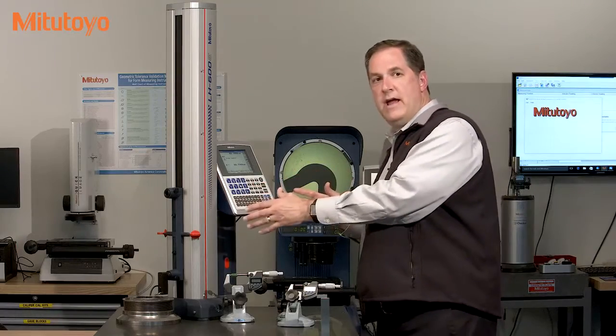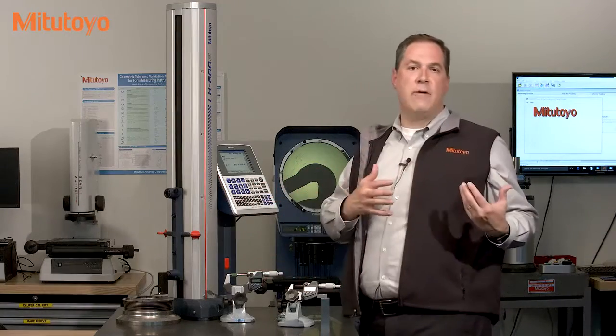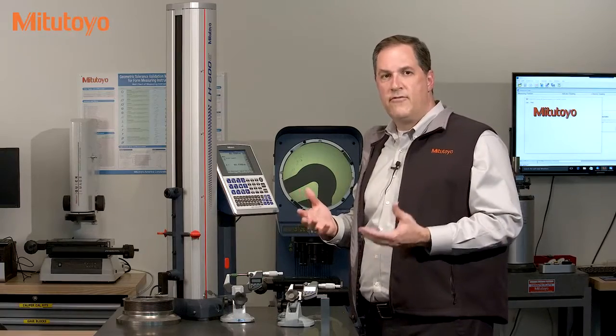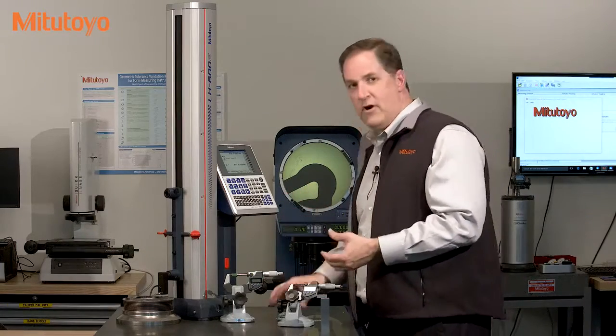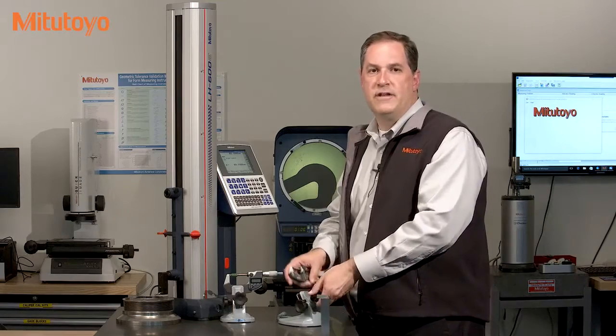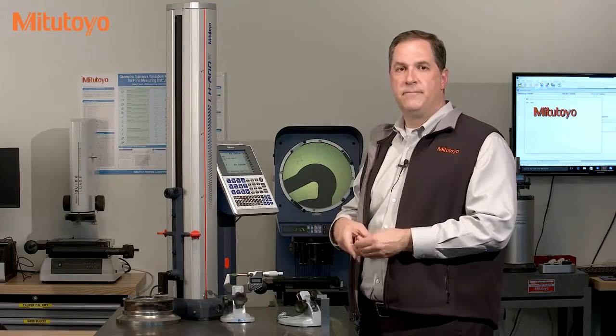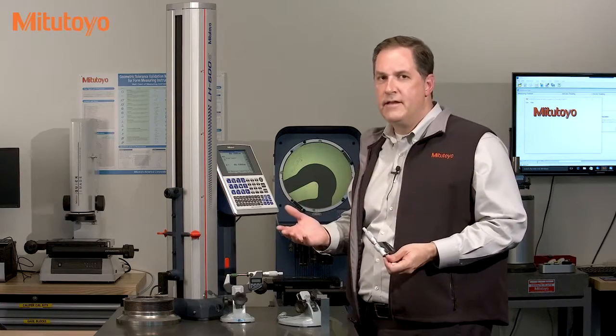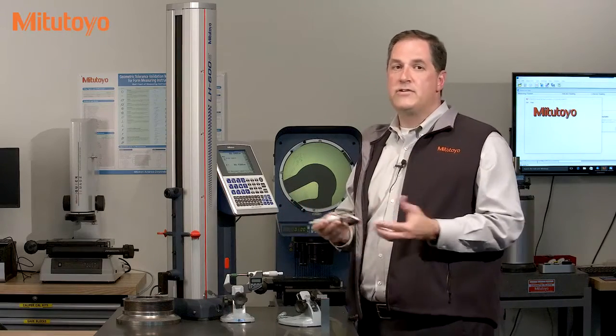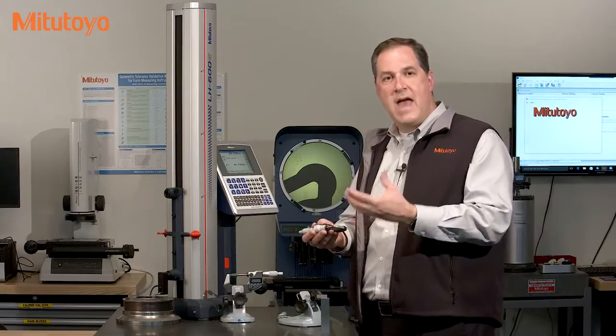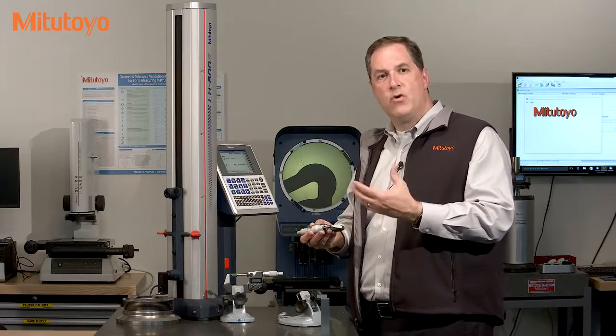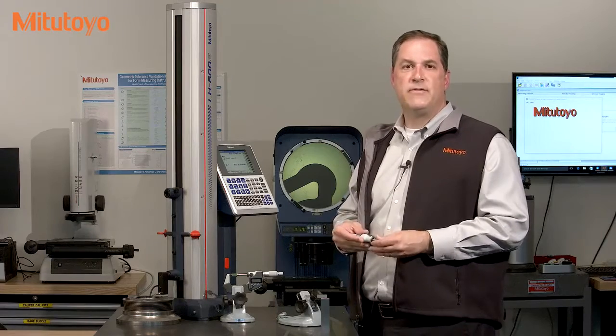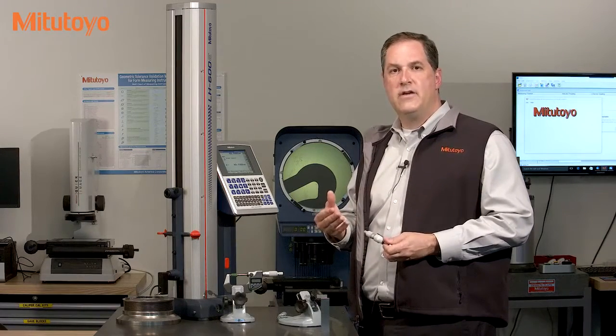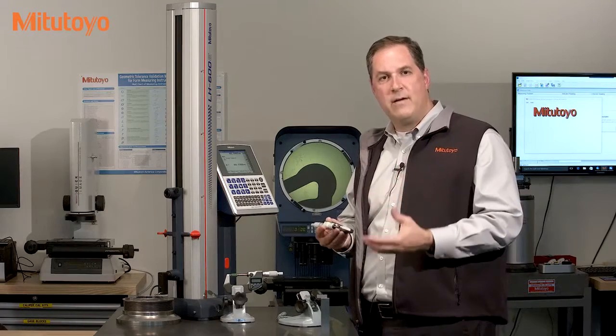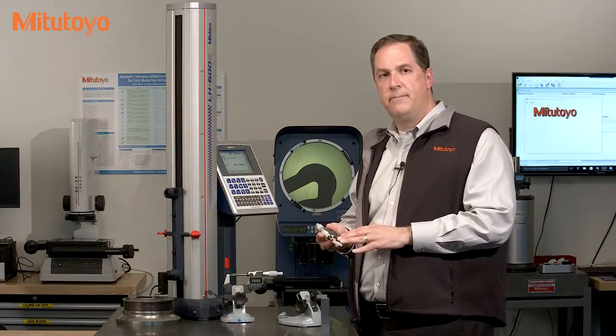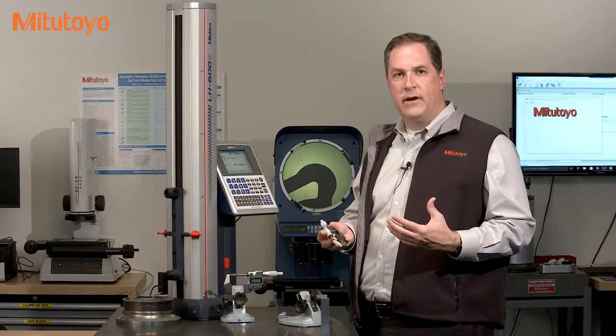So when this linear height or these micrometers leave the shop floor and come in for calibration, the first step is to check it out, to see if it's functioning properly, to assess what's called the as found or as received condition. This is done before any cleaning, before any repair, before any service or adjustments. Checking the as found accuracy is one of the most critical steps in calibration, as it provides the necessary data to understand the stability or the reliability of the measuring equipment over time, since the last time it was calibrated.